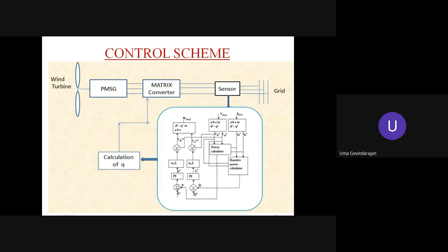Now the overall control mechanism is that we will have independent loops for active power and reactive power. This reference power P star, we can take either from the mechanical side or the electrical side, because this is nothing but the active power available from the machine. Due to the wind electric generation, this P star is being generated. This P star is generated from the wind turbine, coming external to the loop. And Q star is up to us, it is up to the user. If you want to transfer the power at unity power factor, you can make Q star equal to 0.